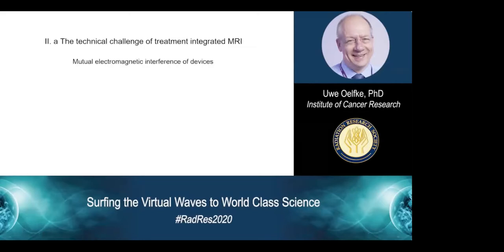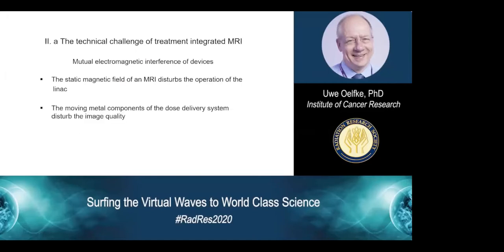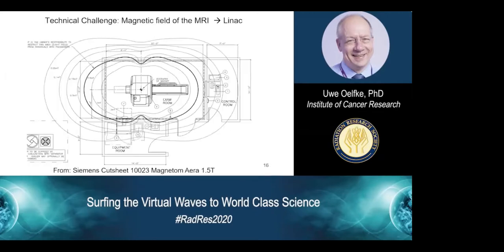It is the mutual electromagnetic interference between these two devices. First, the static magnetic field of an MRI disturbs the operation of the linear accelerator, and second, the moving metal components of the dose delivery system, like the multi-leaf collimator, disturb the image quality of the MRI. We will briefly look at some aspects of both problems.